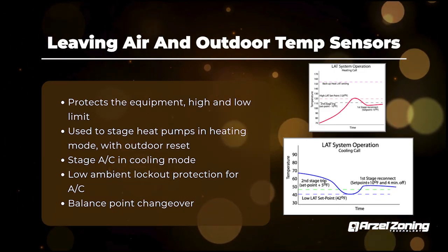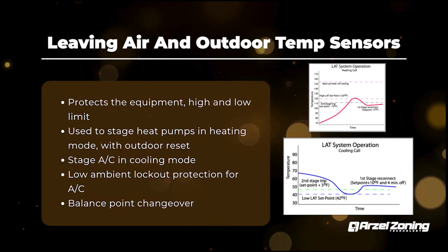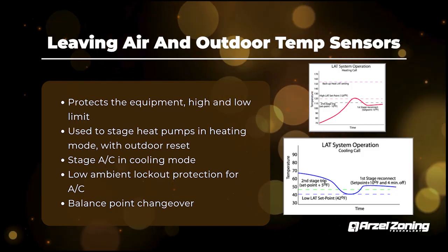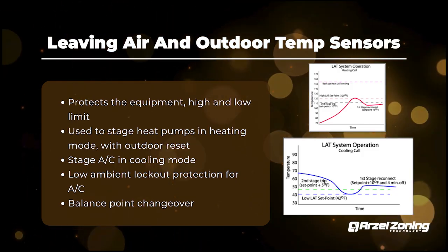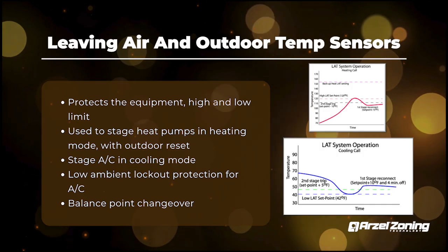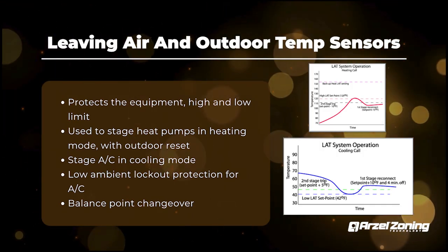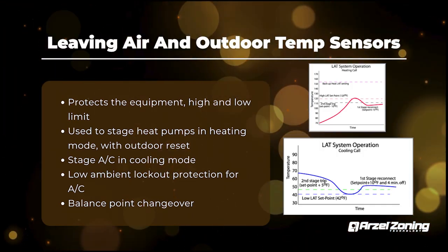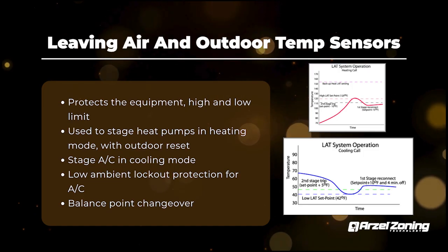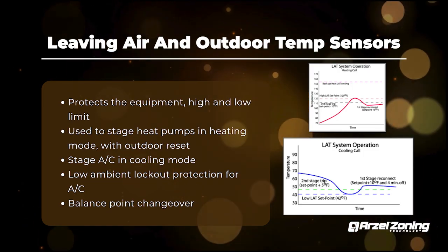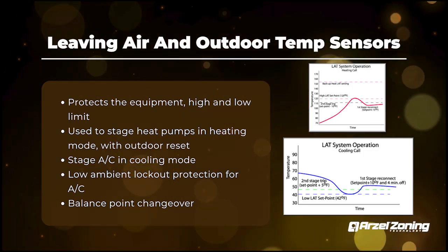So there's a setting for your auxiliary heat, which is going to be your backup heat source. That's for your high temp. And then it's also going to have your high temp for the outdoor heat pump as well. And then it'll have your low temp lockout, so your freeze protection. But also, because of the way the HeatPumPro works, all of the staging is done internally on the panel.